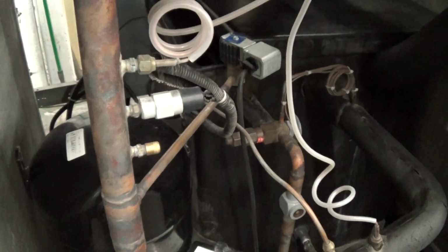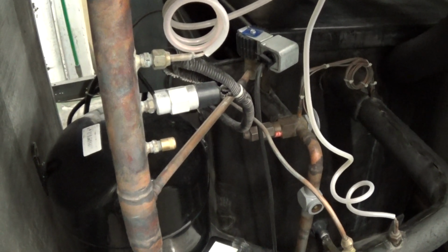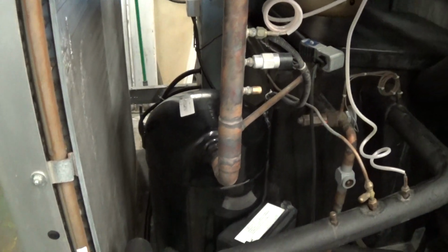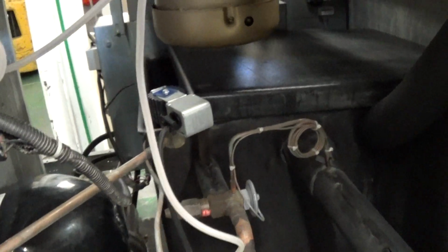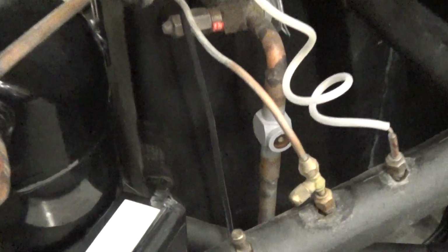That's actually important for this chiller, or just the high pressure topic, because these units have to have their side covers on to run or they will go into high pressure alarm, because the airflow has to come in on the left and the right side condenser, and you've got your hefty single fan and fan blade, and the discharge flows upward. Here we have your refrigerant sight glass, hot gas bypass for capacity control, positive shut-off solenoid and filter dryer. This is an R410A refrigerant machine.